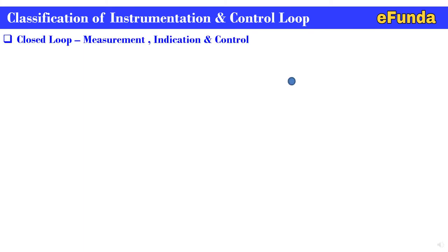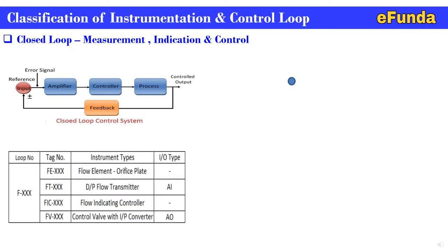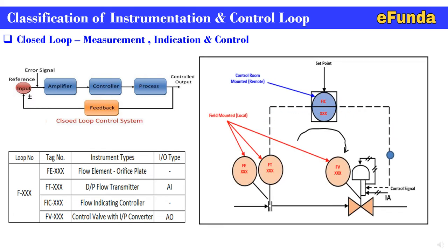Closed loop — measurement, indication and control. One can see the closed loop control system where the input signal is connected to the amplifier, amplifier to the controller, controller to the process, and feedback is taken and connected again with the input so as to compare the feedback and the input. In the table below, the flow loop instruments are shown: FE flow element orifice plate, FT DP flow transmitter analog input to the control room, FIC flow indicating controller, FV control valve with I2P converter having analog output from the control room.